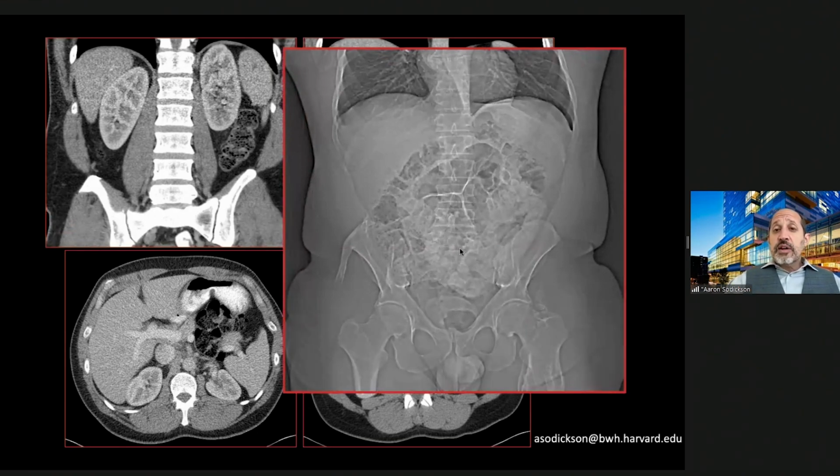This is what the scanner uses to determine the X-ray attenuation as a function of Z position. But then the patient moved. Something happened, they got up, they repositioned, they went about 10 centimeters towards their head, but we did not repeat the planning projection radiograph. And so this is critical. This is what the scanner uses to determine how much X-ray flux to administer.